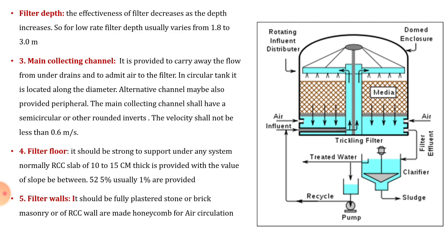Then filter depth. The effectiveness of the filter decreases as the depth increases. So for a low rate filter, depth usually varies from 1.8 to 3 meter.